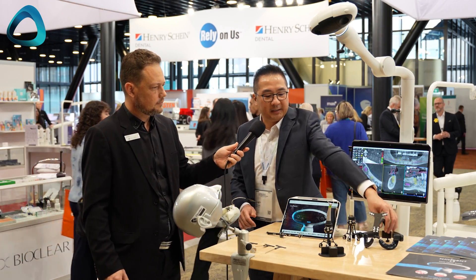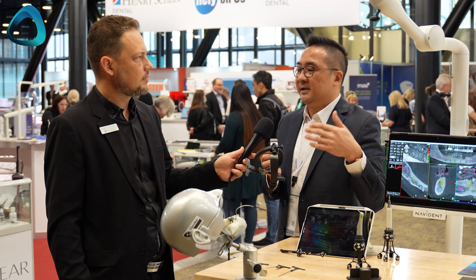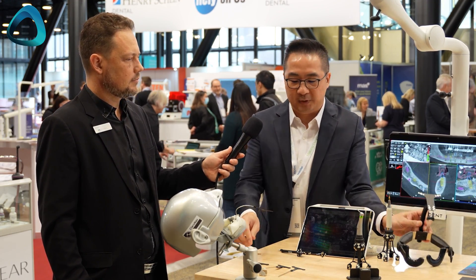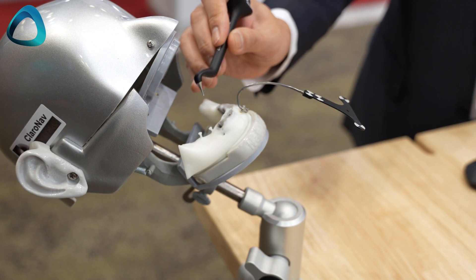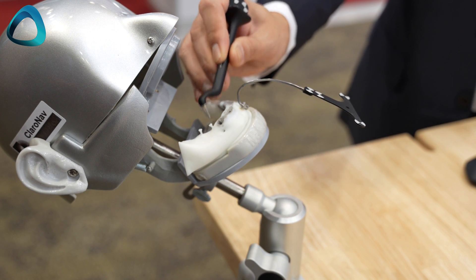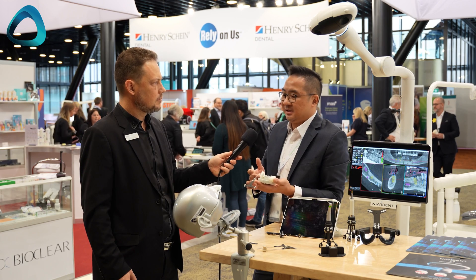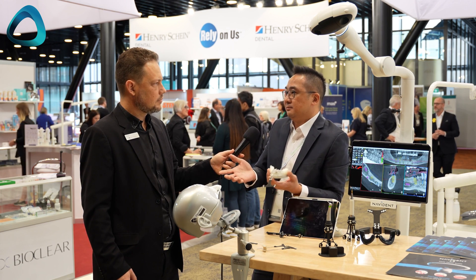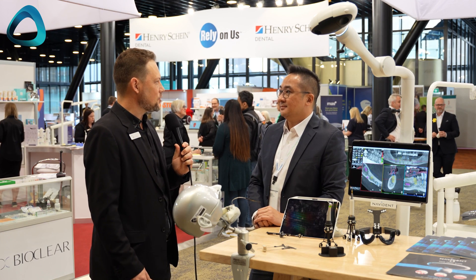There are two patient attachment options. For maxilla surgery — single implant, zygomatic, or pterygoid — we have the head tracker. We also have the jaw tracker, which attaches to the patient's tooth using composite or putty registration material in about one minute. For full dentures, all-on-4, or all-on-6 cases, you can use three 1.5mm bone screws for fixation. Great options covering both maxillofacial and dental applications.